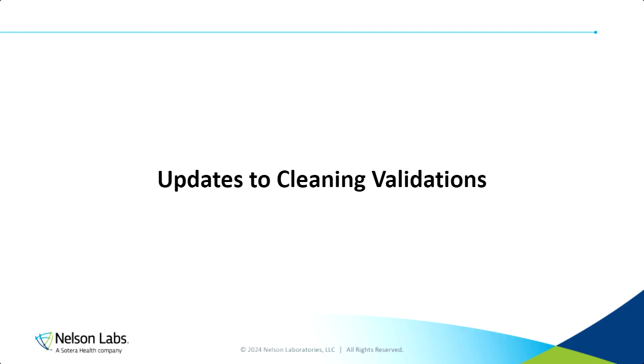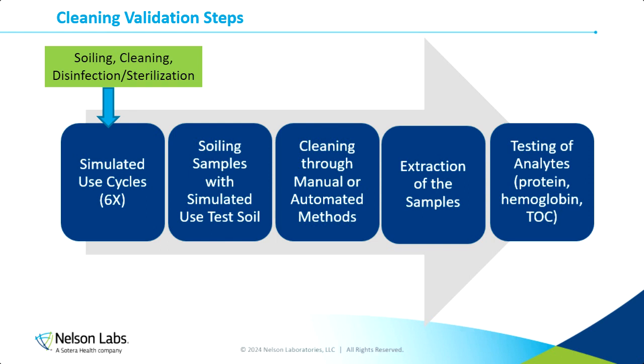All right, so moving on, we are going to talk about the updates to cleaning validations. To start off, a cleaning validation has multiple steps involved, so I'm just going to walk through what those steps are. Typically, the first step is to conduct simulated use cycles. These are repeated cycles of soiling, cleaning, and either disinfecting or sterilizing the device. Once we complete those, we can move into what I like to call the seventh cycle, or the actual cleaning efficacy portion of the test.